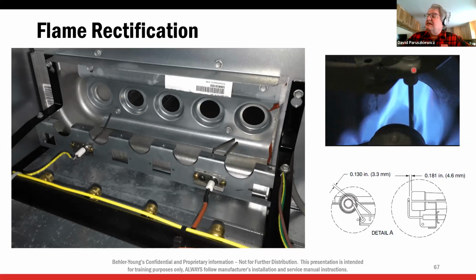If this ceramic is cracked, it could be bad. If this wire is bad or shorted or broken, or the gap. This is the gap between the igniter and the electrode, or the igniter and the ground, right here, side to side and in front of the burner. What happens if that igniter is touching the burner? Well, it can't spark, right? It's shorted to ground, so we can't spark. We're not going to ignite.